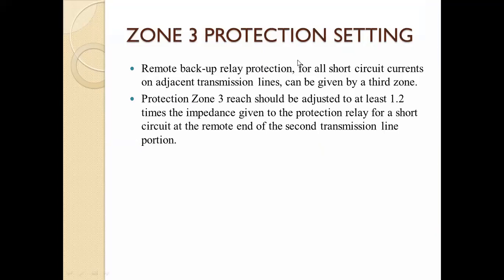Zone 3 reach should be adjusted to at least 1.2 times the impedance given to the protection relay for a short circuit. So whatever impedance is given, just multiply by 1.2 there. That will be the setting point for your third zone.